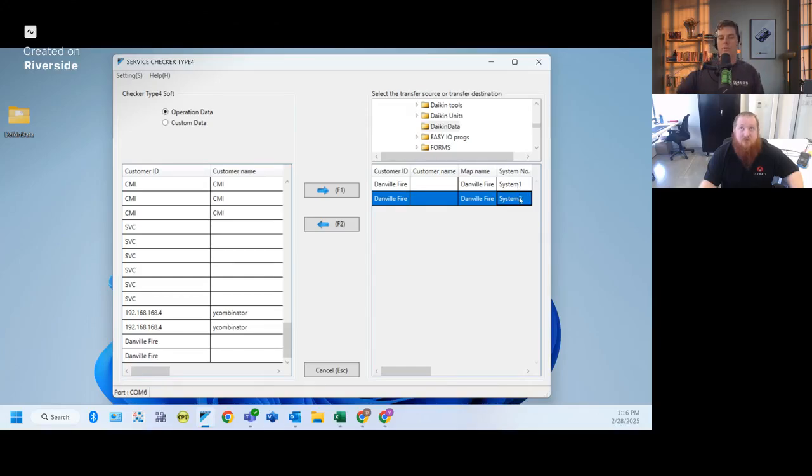So why is that important to understand? Because when you send someone the data and you don't know what system number it is in that pecking order, they've got to go through 8 sets of data to find out which system really has the problem. So that's where the AirNet address on your outdoor unit comes in, setting mode 113 or 213 to change that AirNet address on the outdoor unit so that you can see what module you're actually working on. Write it in your service ticket notes, or write a note on your phone saying, when I went to this job on this day, I was looking at system 1 out of 4 when I looked at the Service Checker data.